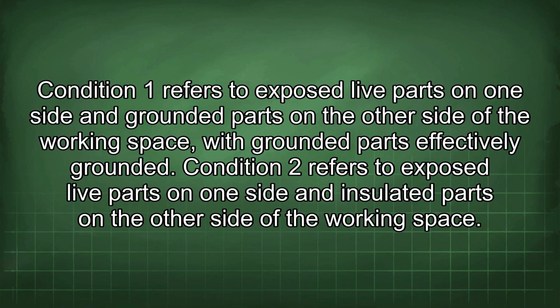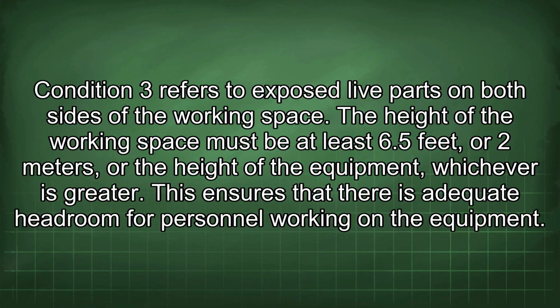Condition 1 refers to exposed live parts on one side and grounded parts on the other side of the working space, with grounded parts effectively grounded. Condition 2 refers to exposed live parts on one side and insulated parts on the other side of the working space. Condition 3 refers to exposed live parts on both sides of the working space.